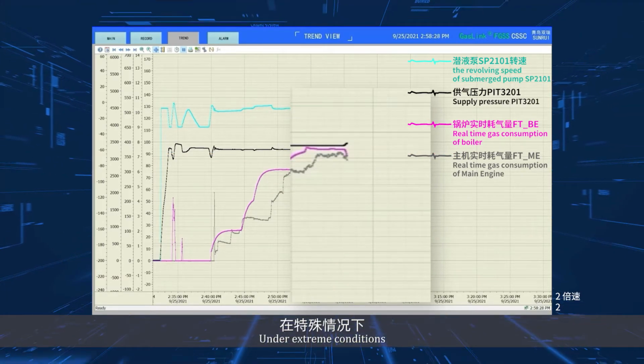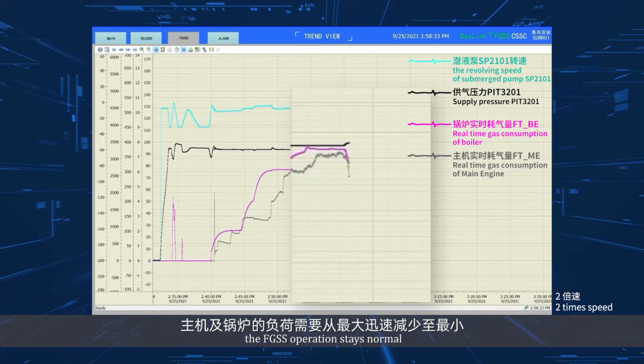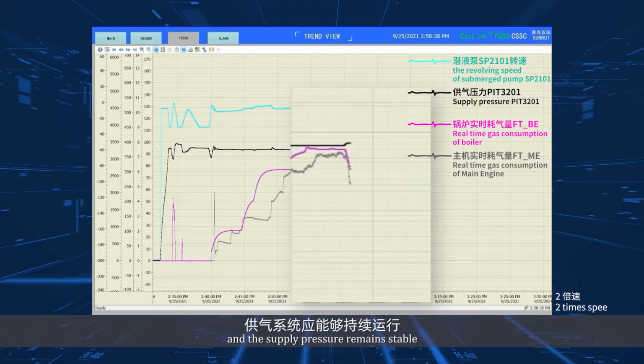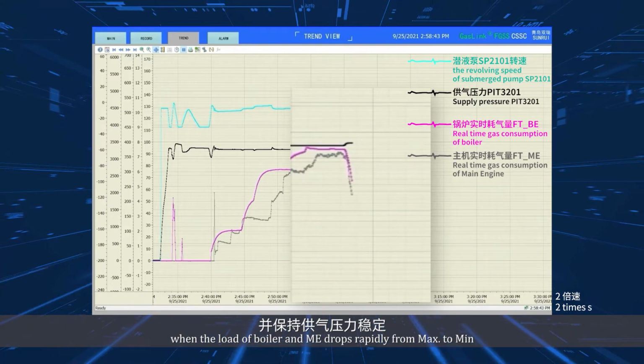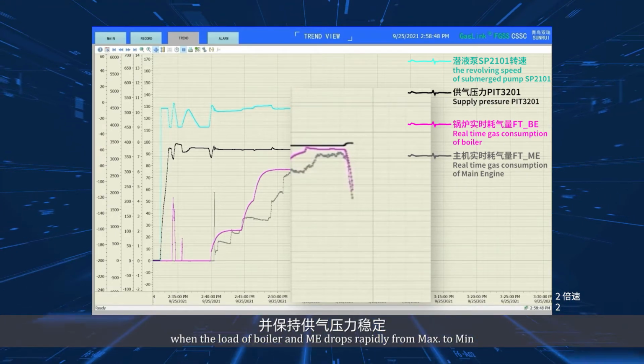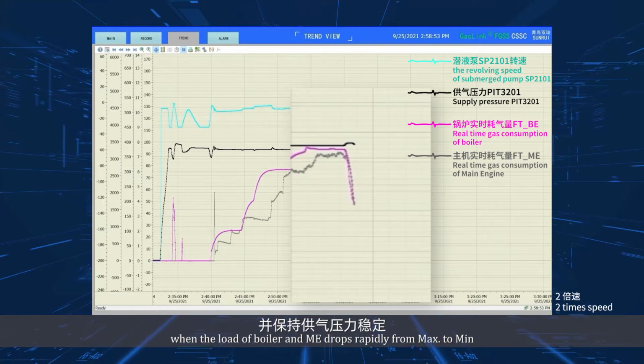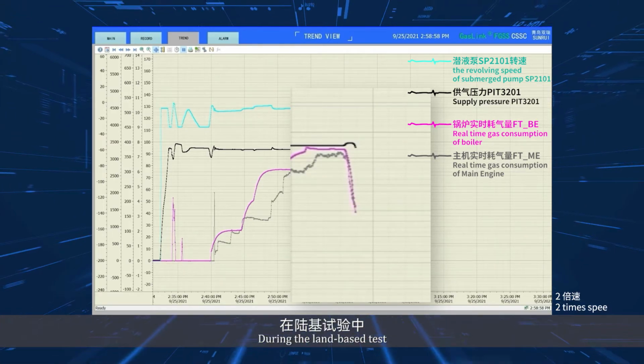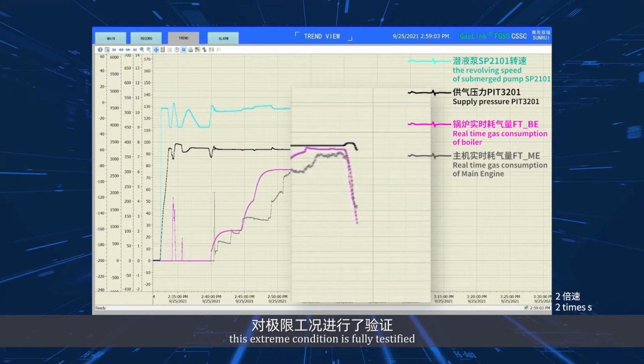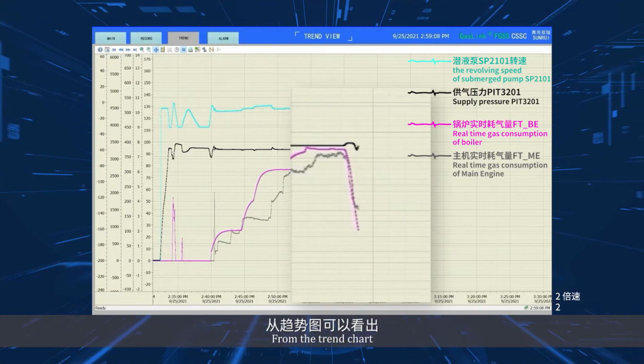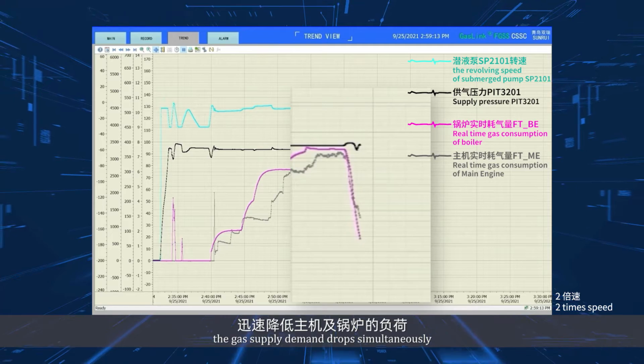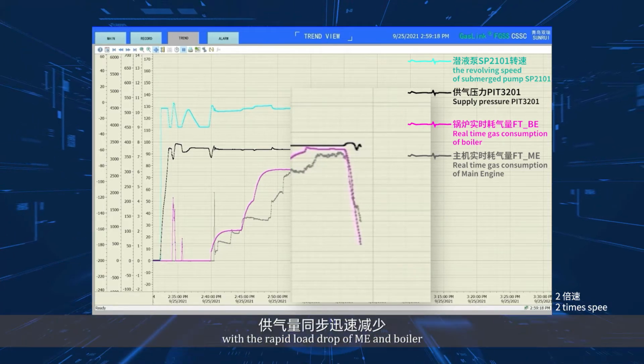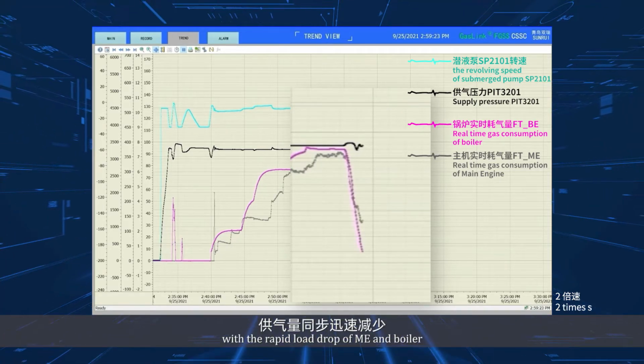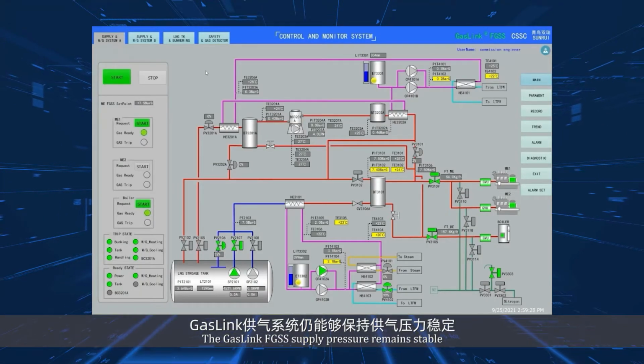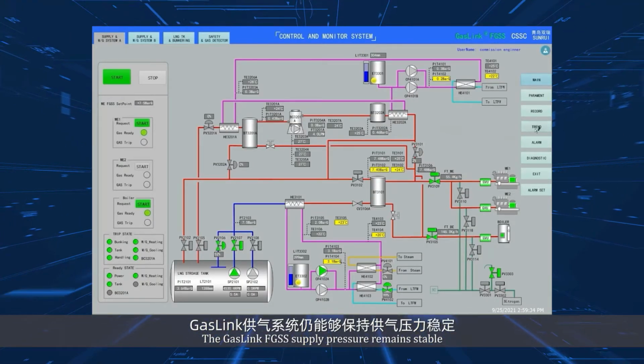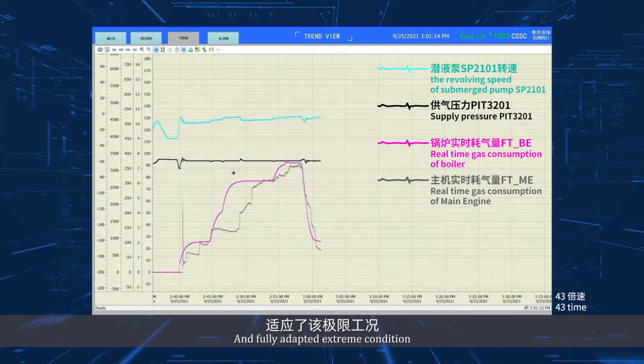Under extreme conditions, the FGSS operation stays normal and supply pressure remains stable when the load of boiler and ME drops rapidly from maximum to minimum. During the land-based test, this extreme condition is fully testified. From the trend chart, the gas supply demand drops simultaneously with a rapid load drop of ME and boiler. The Gaslink FGSS supply pressure remains stable in a fully adapted extreme condition.